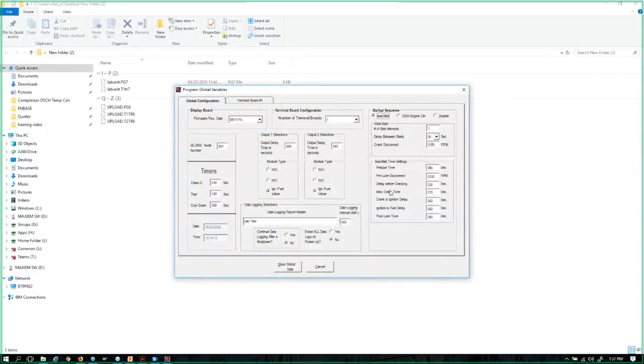Because if I'm out at 1 o'clock in the morning trying to start a unit and it fails to start a few times and doesn't even try to start, I now have the ability to go and push the reset button on the face or the keypad of the DE-3000 to turn these two outputs on instantly, and gives me an opportunity to go and investigate. Is my fuel doing what it's supposed to do? Is my ignition doing what it's supposed to do? Because we can use these outputs to, yes, ground a G lead for the ignition, or we can also use these outputs to power an ignition system, such as a CPU95, a CD200 ignition system, etc., etc. Any questions on that?